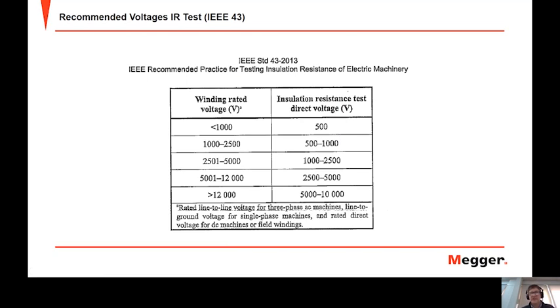If our motor is 3.3 kV, then we'd be in this third row. So the correct voltage for an IR test on a 3.3 kV motor is 1,000 volts or 2,500 volts DC. So these are the standards that you should be following when you're testing your motors.